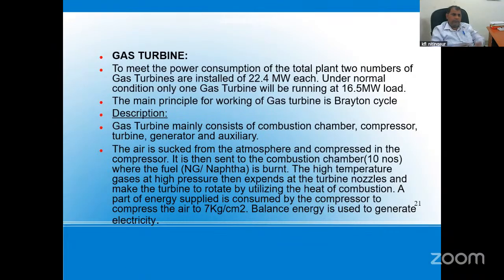Now, gas turbine. I explained earlier that our plant is running on a continuous and constant load. We cannot depend on an outer agency to supply the power. Hence, our own power plant is set up. We have two gas turbines of 22.4 megawatt capacity each. Actually, our plant requirement is only 16 to 17 megawatt load.